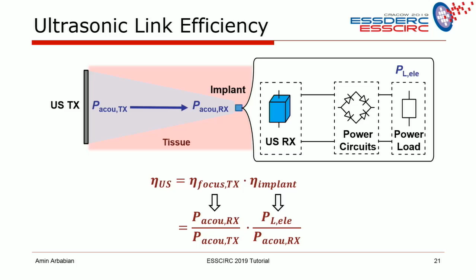Let me start with the implant side of things, and I'll go to the transmitter next. So on the implant side of things, we have the efficiency of the receiver has 4 components. It has the aperture efficiency. I'm going to talk about what aperture efficiency is. Essentially, aperture efficiency is how much of the received available power intensity were you able to pick up from an acoustic to electrical point of view. There's no rectification yet. It's just picking up from acoustic to electrical. And you're normalizing to the available power intensity that's available at that aperture. Right? So that's the aperture efficiency. It's exactly the same definition, by the way, if you've ever designed antennas, it's the same thing.